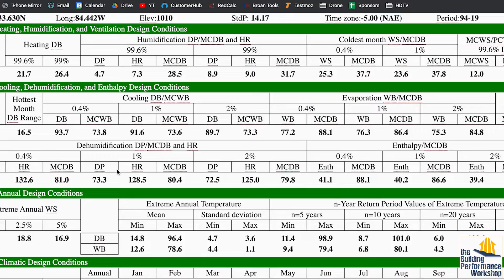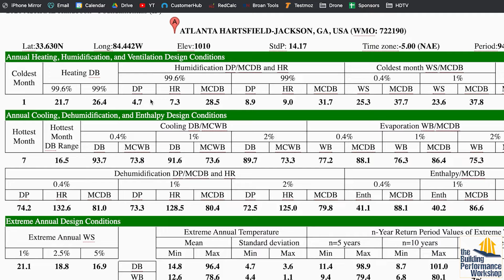They use the mean coincidental wet bulb. But when you talk about the dehumidification day, you look at the dew point and the mean coincidental dry bulb. In some climates, that dew point is going to be way higher than the dew point of your design day, and in some of those same climates, the outdoor temperature will be extremely low compared to your outdoor dry bulb day.